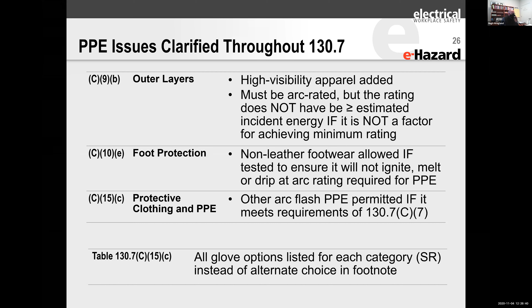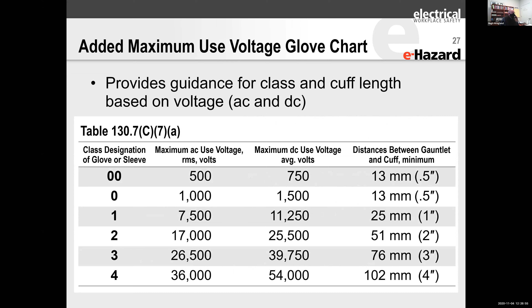Protective clothing PPE, other arc flash PPEs permitted if it meets the requirements of 130.7. Just gives you a little more freedom if you have some oddities that you need that are not arc rated. And then also glove options listed in the category instead of the alternative choice in the footnotes. So there's just a little more clarity, a little more openness in some of the places where we needed that for different work situations. Then they added a maximum use voltage chart. This is already in the ASTM standard that was cited, but they went on and put it right directly in the standard, which is useful.